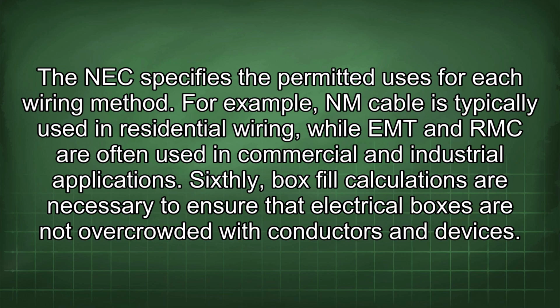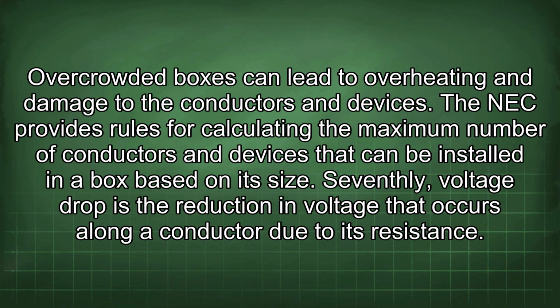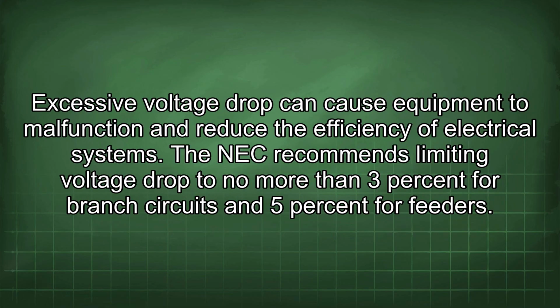Sixthly, box fill calculations are necessary to ensure that electrical boxes are not overcrowded with conductors and devices. Overcrowded boxes can lead to overheating and damage to the conductors and devices. The NEC provides rules for calculating the maximum number of conductors and devices that can be installed in a box based on its size. Seventhly, voltage drop is the reduction in voltage that occurs along a conductor due to its resistance. Excessive voltage drop can cause equipment to malfunction and reduce the efficiency of electrical systems.